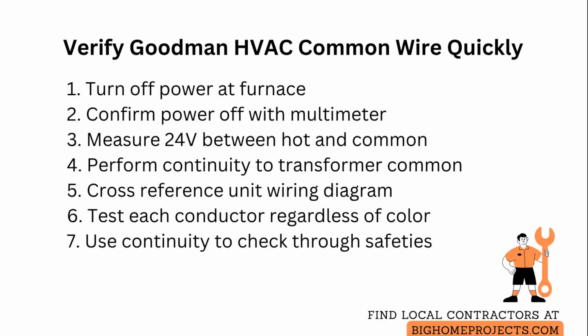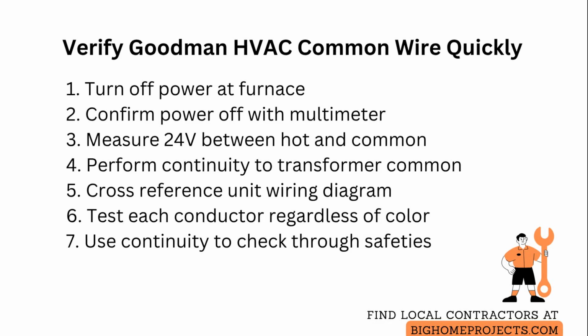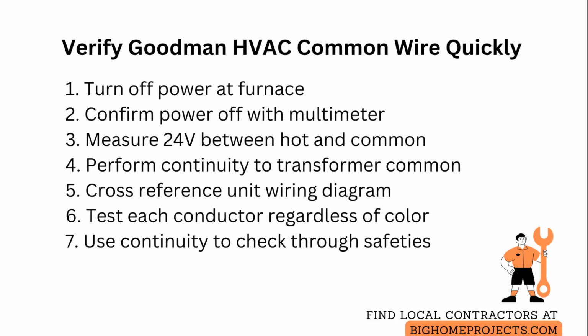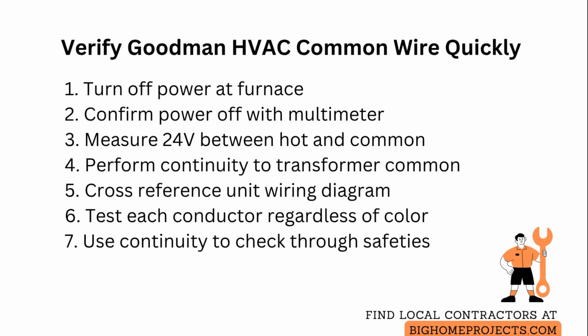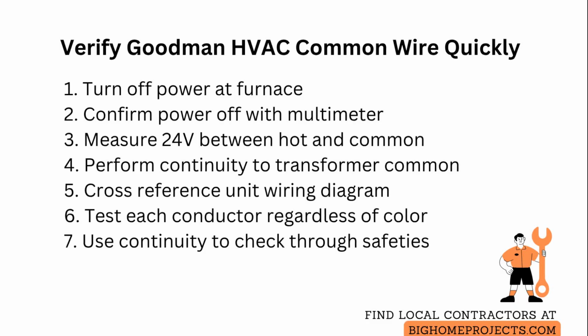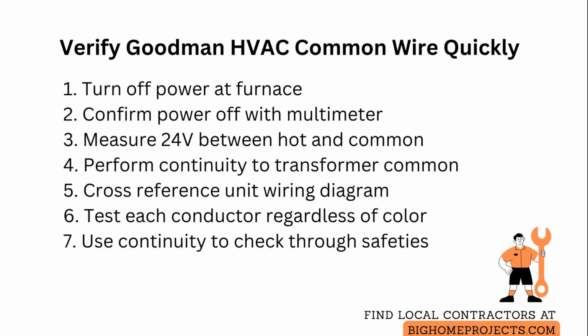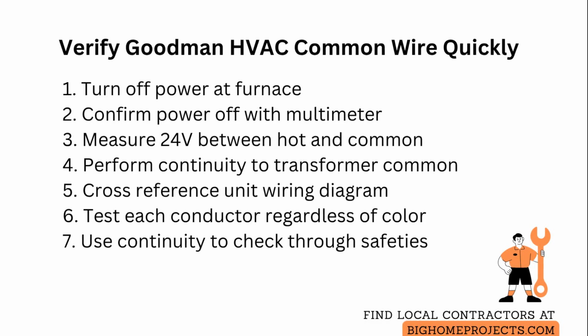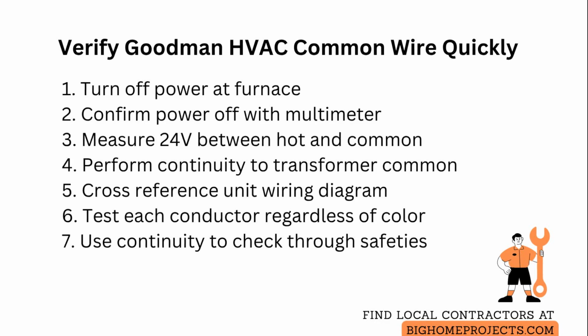Cross-reference the unit wiring diagram printed on the furnace or in the service manual to ensure the terminal labeled common or C corresponds to the same conductor you tested. When the wiring harness uses multiple colors, do not assume color equals function. Verify each conductor individually. If you cannot reach the transformer safely, use a continuity tester between the suspected common and the compressor contactor coil common. Bearing in mind, some systems route commons through safety devices, so continuity may be interrupted when safeties are tripped.